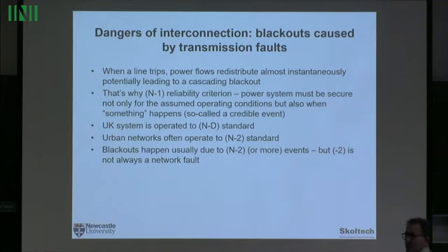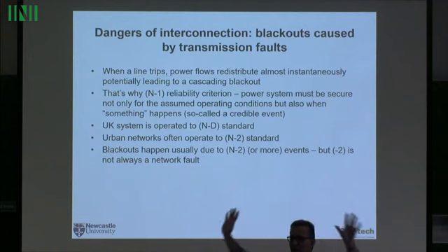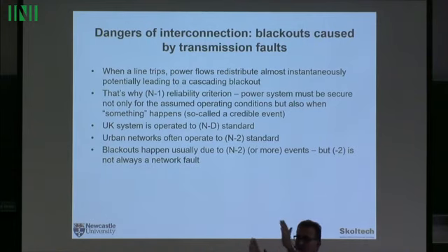Could you explain quickly what exactly this N-2 is? Right. So, how do those cascading blackouts start? You have line trips. Due to the principles I mentioned, the power flow in the network depends on what's going on everywhere else. So if a line trips, power flow is distributed to other lines instantaneously. The other lines may get overloaded, and then disconnect.